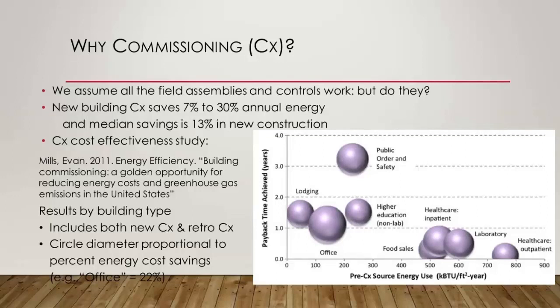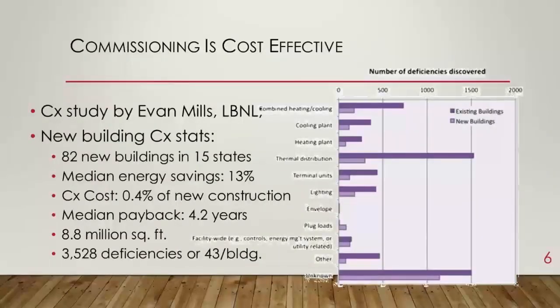And you can see on this graph what kind of payback time we get related to the energy use index of the buildings, with the circles here being larger when there's more savings. And this graph is interesting. It shows the number of deficiencies discovered in the buildings, and we can see that it's pretty high. This is based on 82 new buildings in 15 states. And well, we've got both new and retrofit buildings shown there. So the lighter bars are the new buildings.